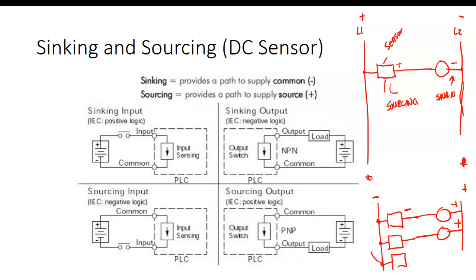And so you can get these two different ways. The problem is, if your loads are connected to minus, and then you get a sinking sensor, it's not going to work. It's not going to hurt it, right? You understand that? It's just not going to work, because it's trying to provide the minus, and you've got a minus reference on your load.